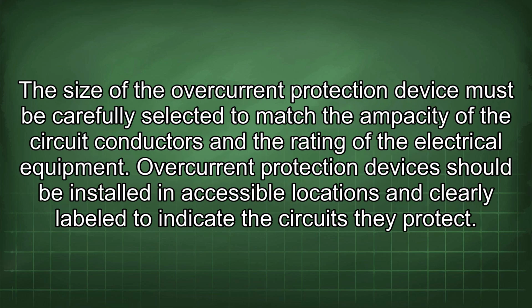The size of the overcurrent protection device must be carefully selected to match the ampacity of the circuit conductors and the rating of the electrical equipment.